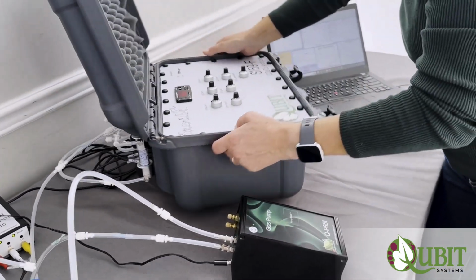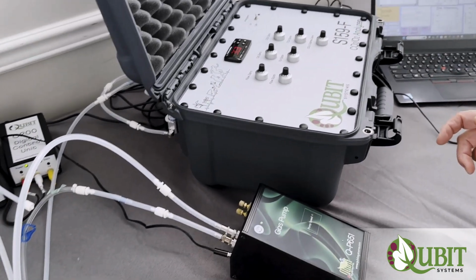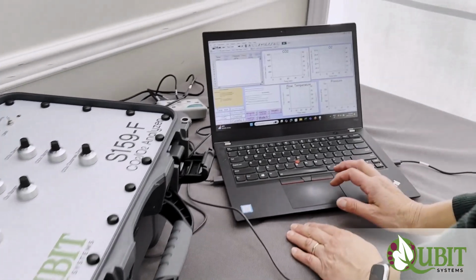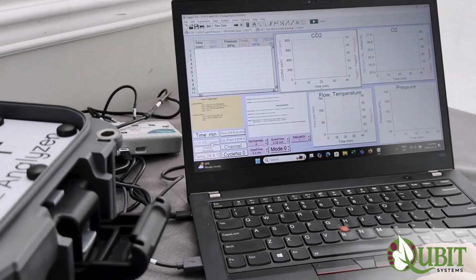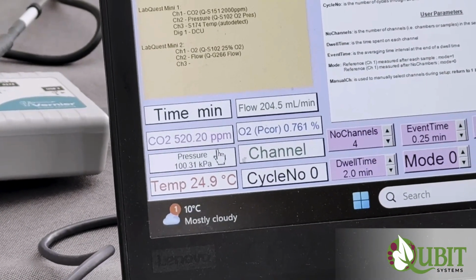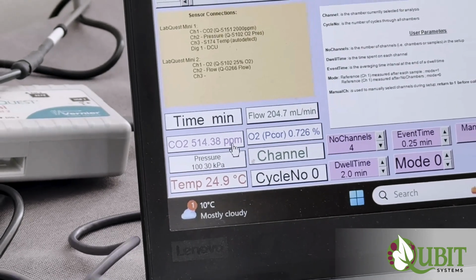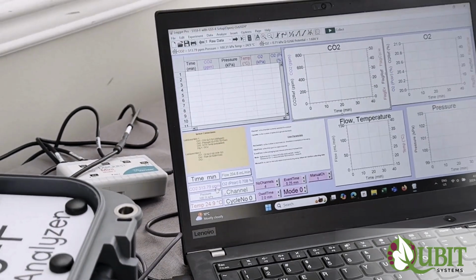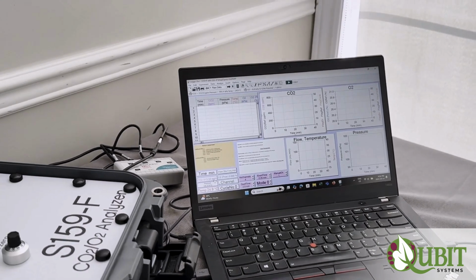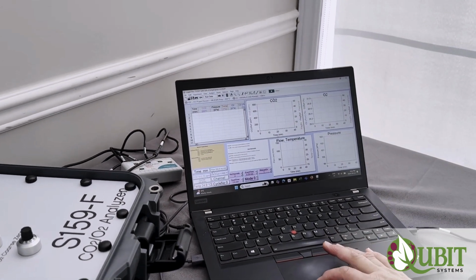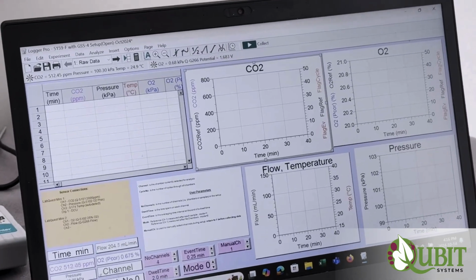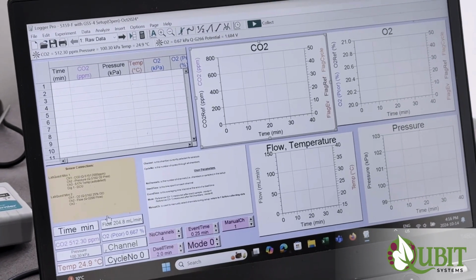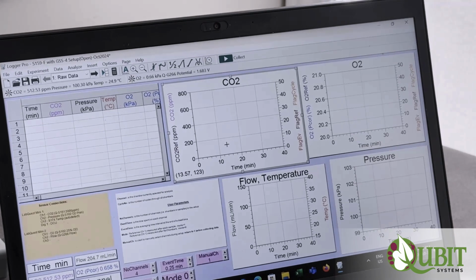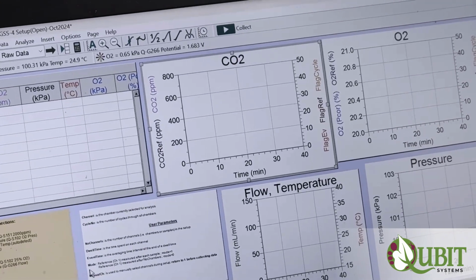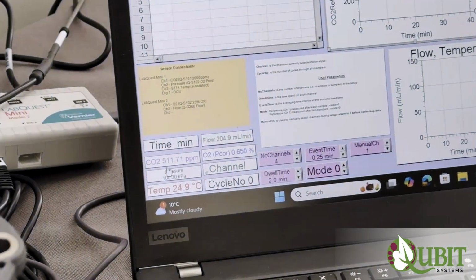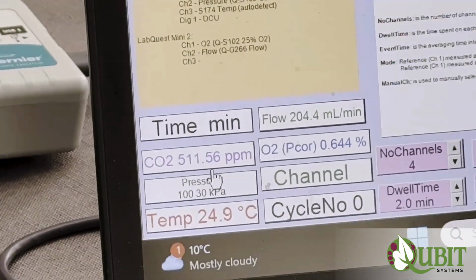It is important to know the exact level of CO2. You then come to your readout of CO2, the meter in the software, and you wait for that to stabilize. If this reading is different than 505 ppm, then we will adjust it on the analyzer. And during this calibration process, notice that we're not collecting any data. I'm just simply looking at these meters. However, if one wanted to, you could start collecting data just to have a record of how you've adjusted things. So you can see the CO2 is stabilizing around 511 parts per million.